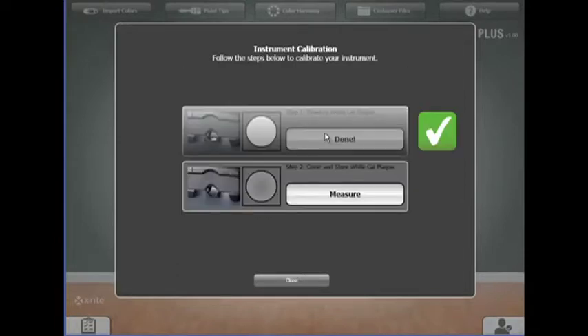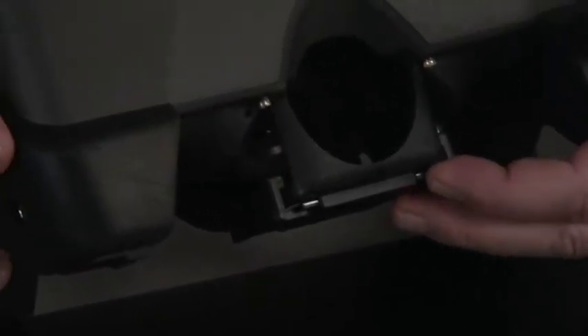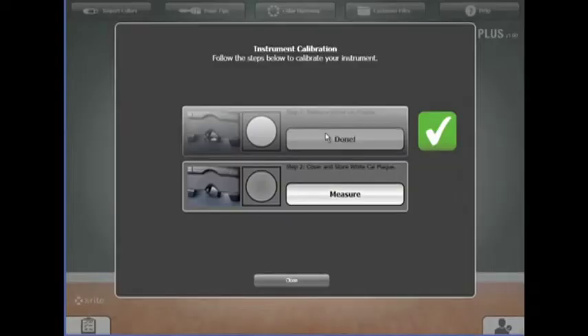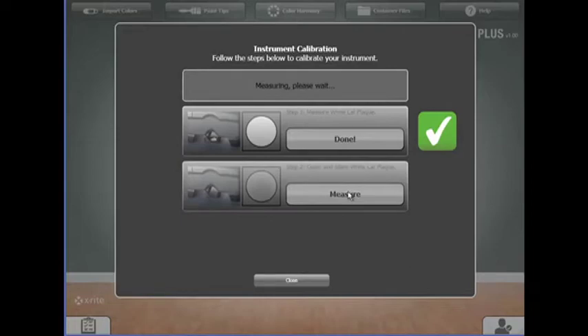Once complete, slide the calibration plaque back into its lock position. Place the instrument down on the black mat, then click on step two, measure.